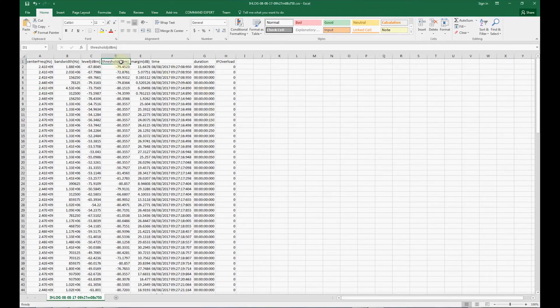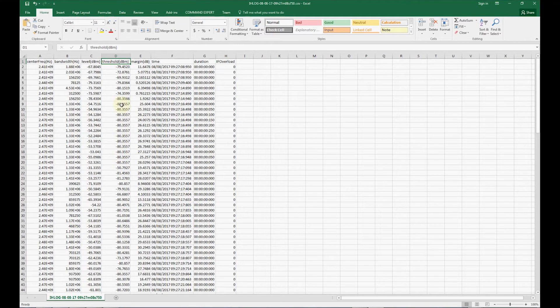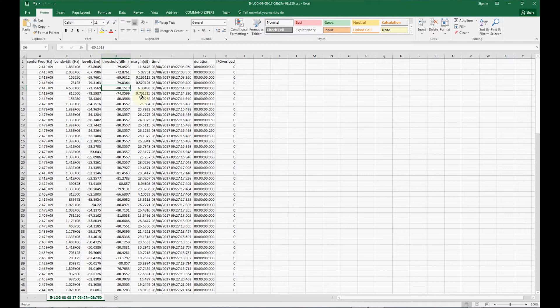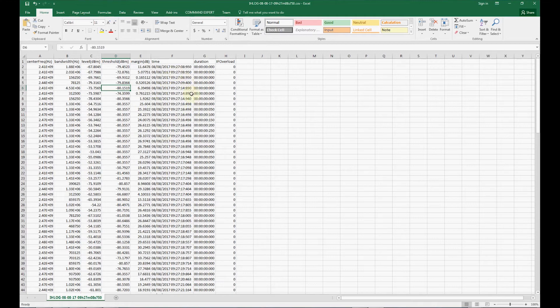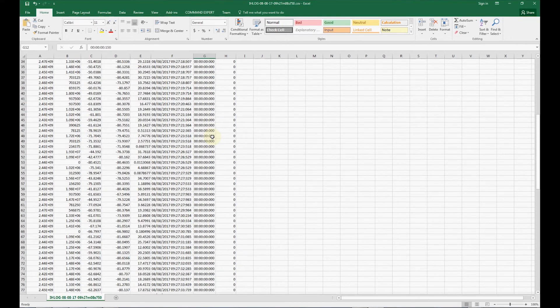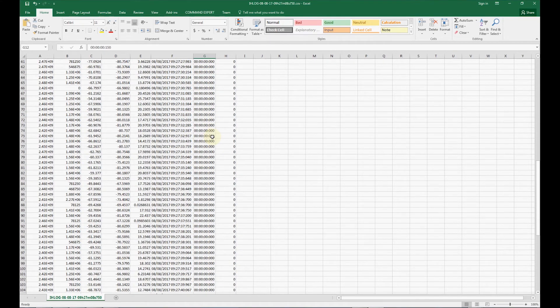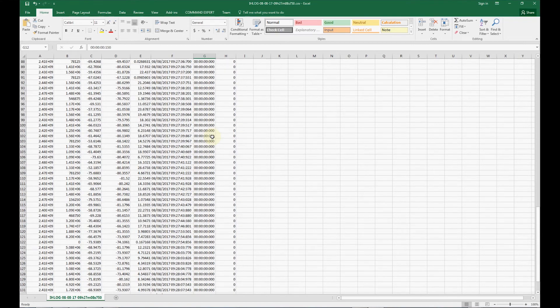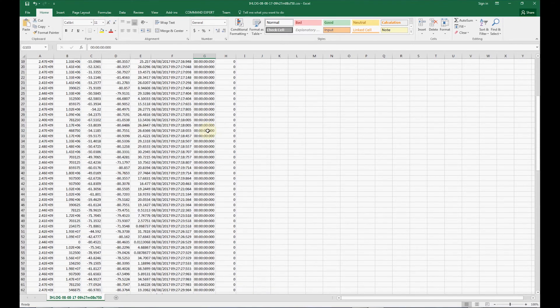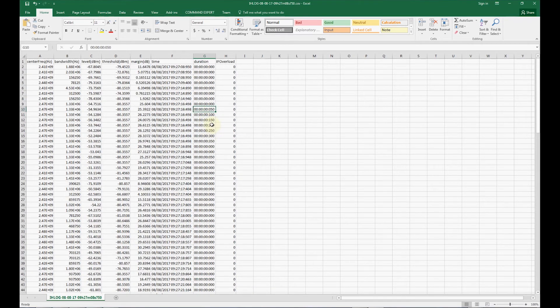So threshold refers to, that's the amplitude value that was a threshold of the baseline at the frequency point. And then margin is going to be basically the number of decibels above the threshold that the peak level of that event was. So even if you have the level set to channel power, this is still going to use the peak level to make that calculation. And then the time that the event occurred is here. And the duration, see these are all very brief events. So they're actually registering as zero. We've got some slightly longer ones. And then a couple hundred milliseconds. These are like blips. Which basically mean, what zero actually means is that it was just one sweep that they existed for. These persisted over multiple sweeps.